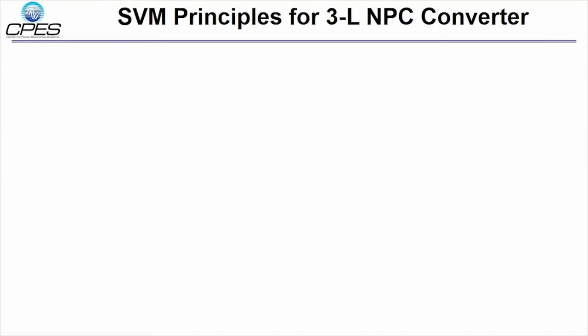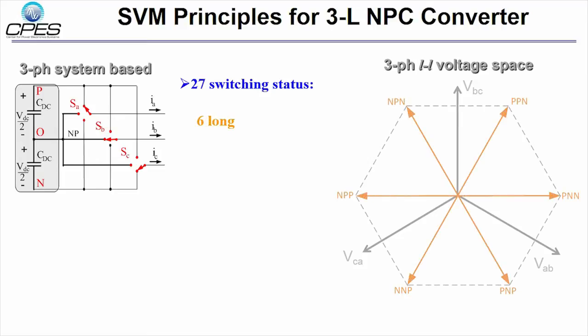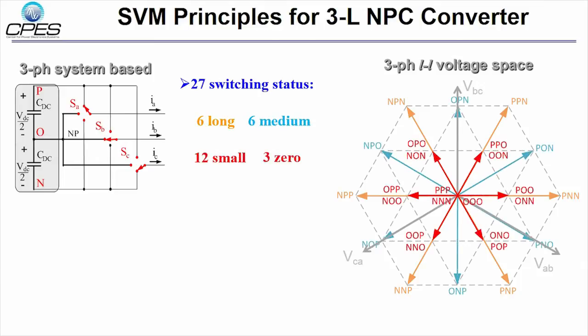For the 3-level NPC converter, each phase leg is a 3-pole switch. The 3-phase system has total 27 switching states with 6 long, 6 medium, 12 small, and 3 zero vectors. The rotating voltage reference can be synthesized by the nearest 3 vectors.